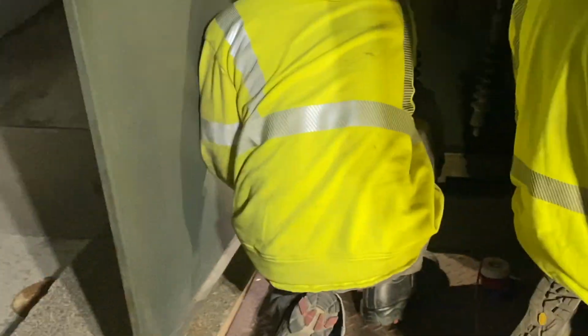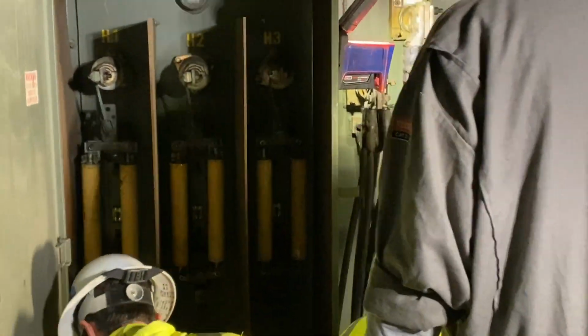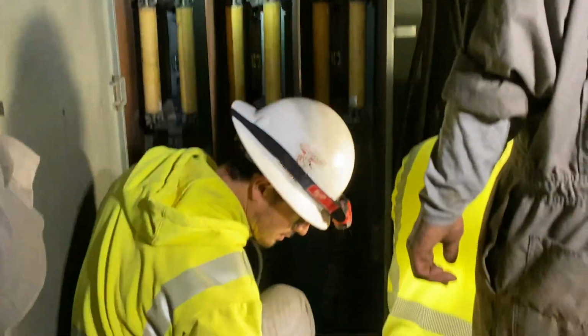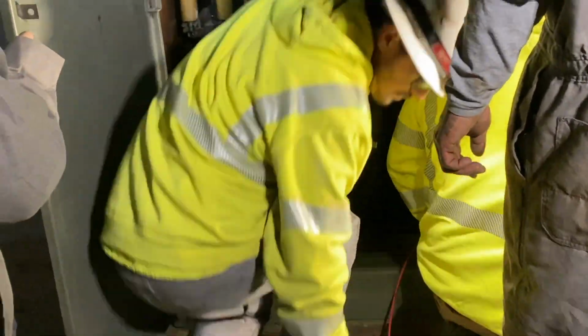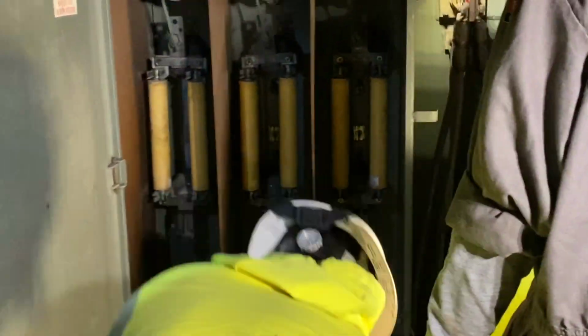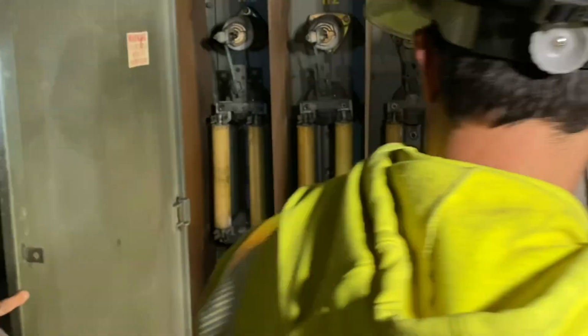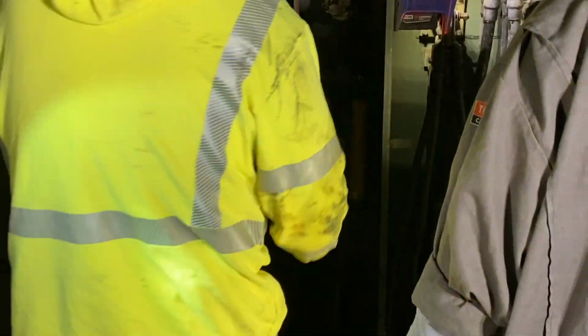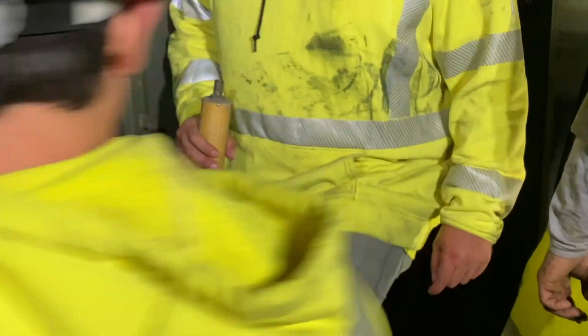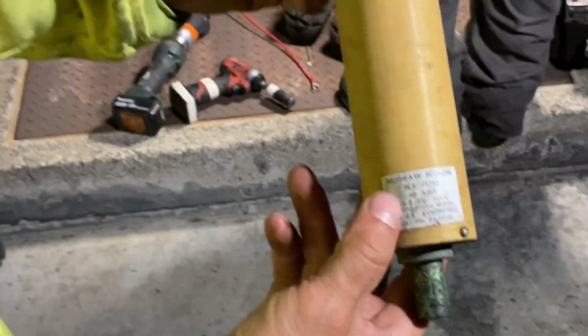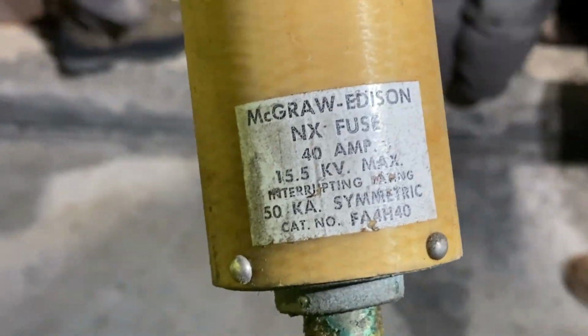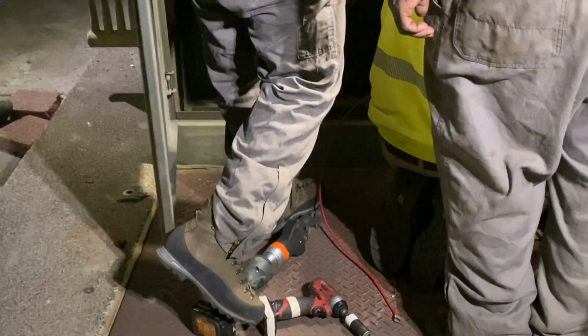But best believe, before we conduct any kind of maintenance or repair work on high voltage systems like this, we make sure that the whole system is de-energized and what we call isolated. It's called electrical isolation. And there's also lockout and tagout procedures to prevent any accidents while work is being performed, like re-energizing the system by accident. We make sure the system is also properly grounded as well.